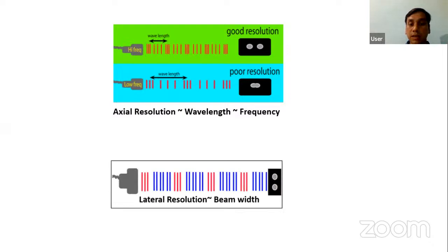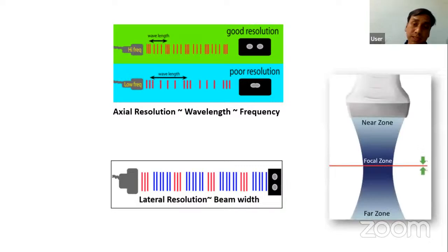And what is lateral resolution? Lateral resolution is when the two structures are present perpendicular to the ultrasound beam, and it depends upon the beam width. So what do we mean by beam width? The ultrasound beam has basically three zones: a near zone, then it converges to the focal zone, then it widens out in the far zone. To get the best resolution, you have to place your object of interest in the focal zone. In the focal zone, the beam width is the least, and you'll get the best resolution.